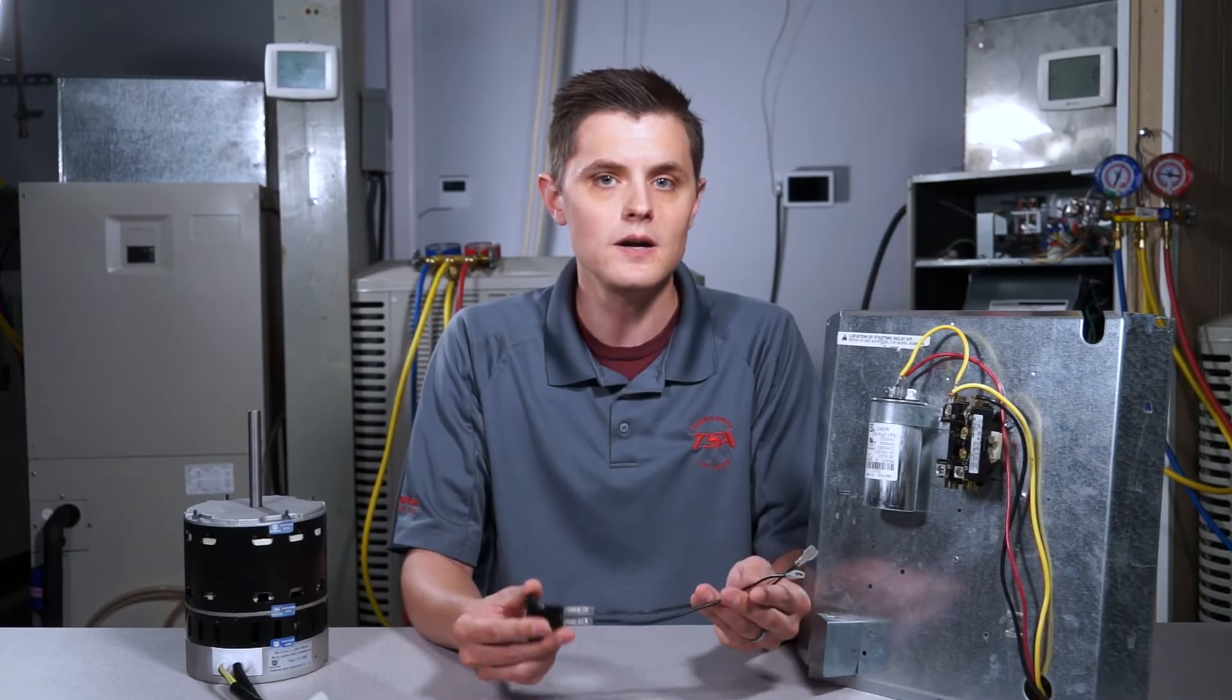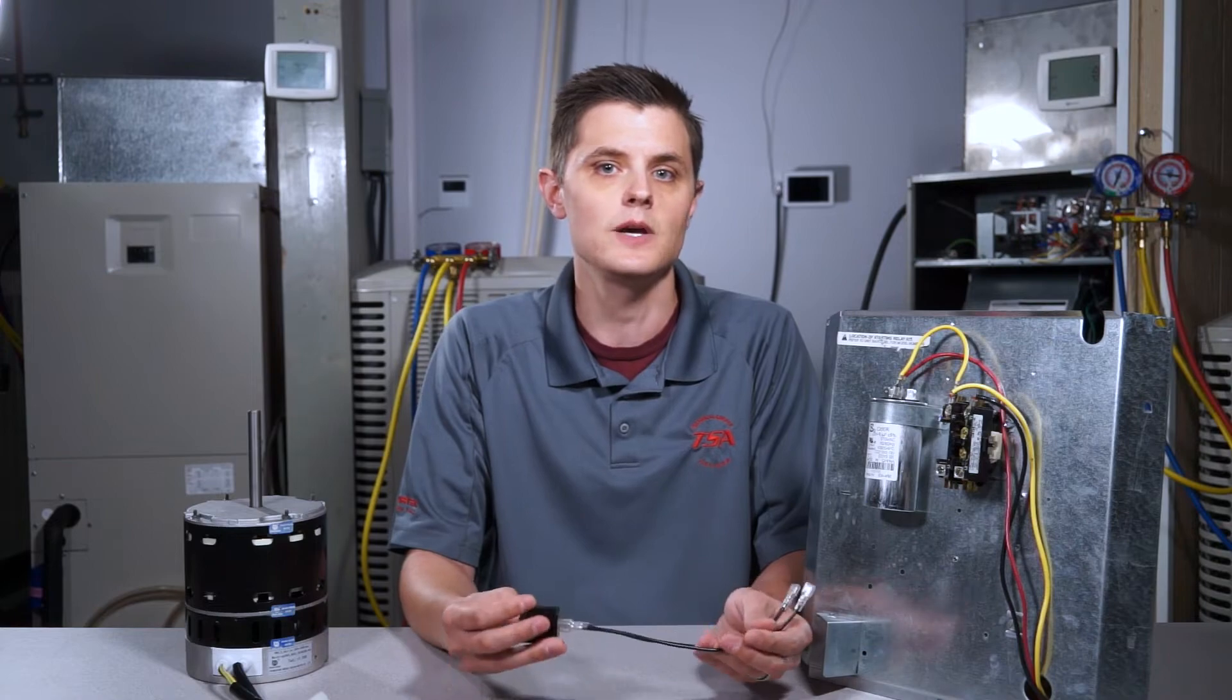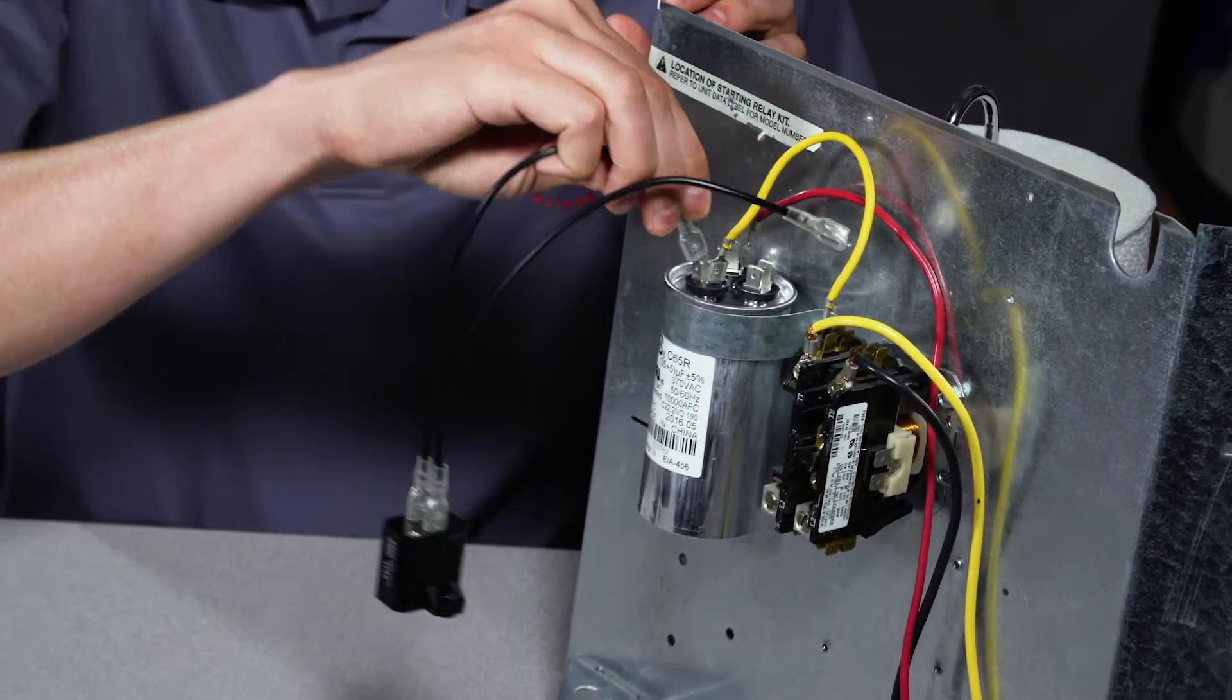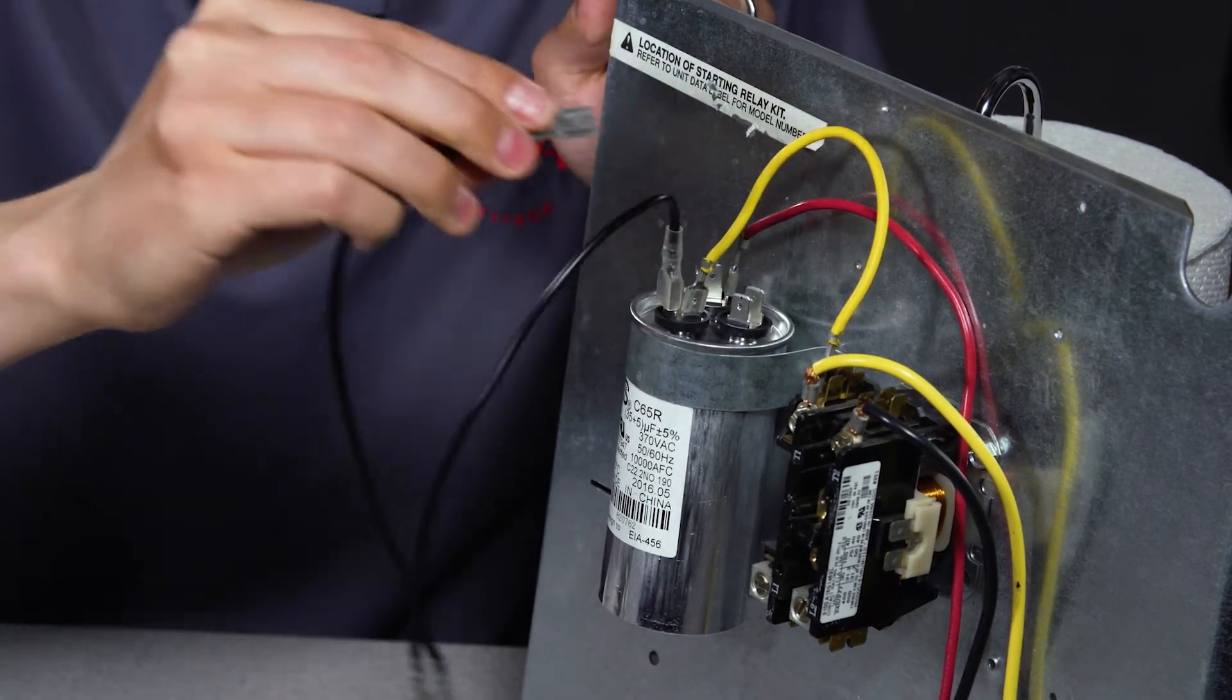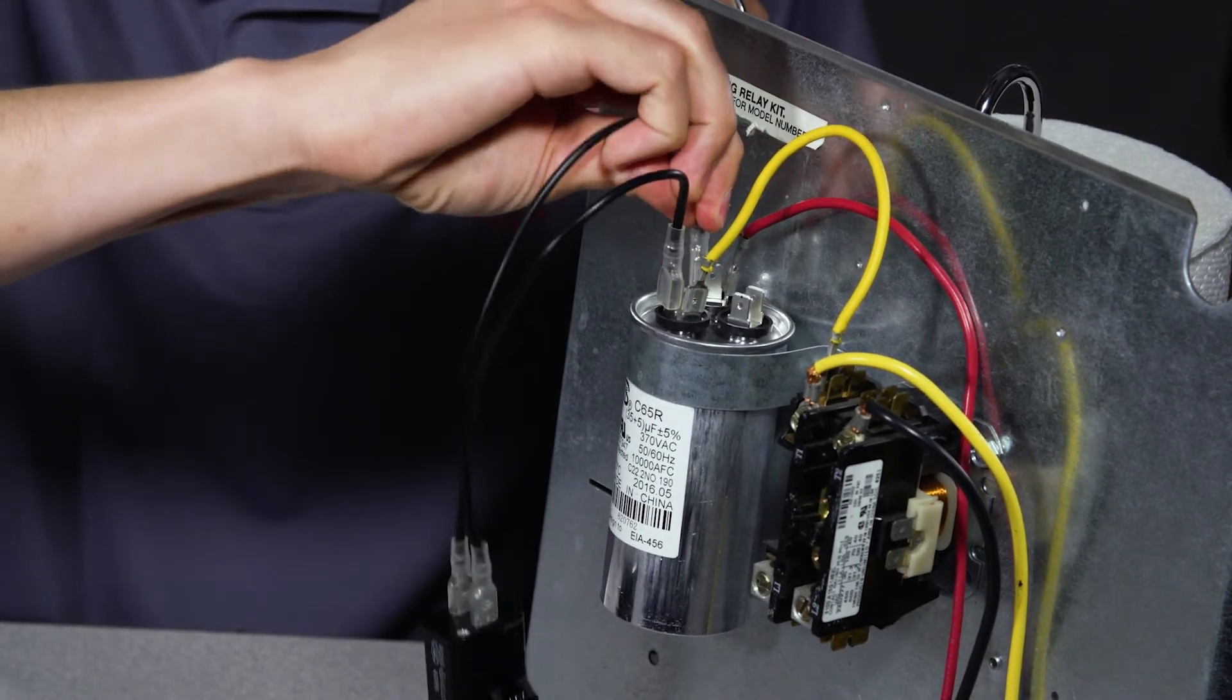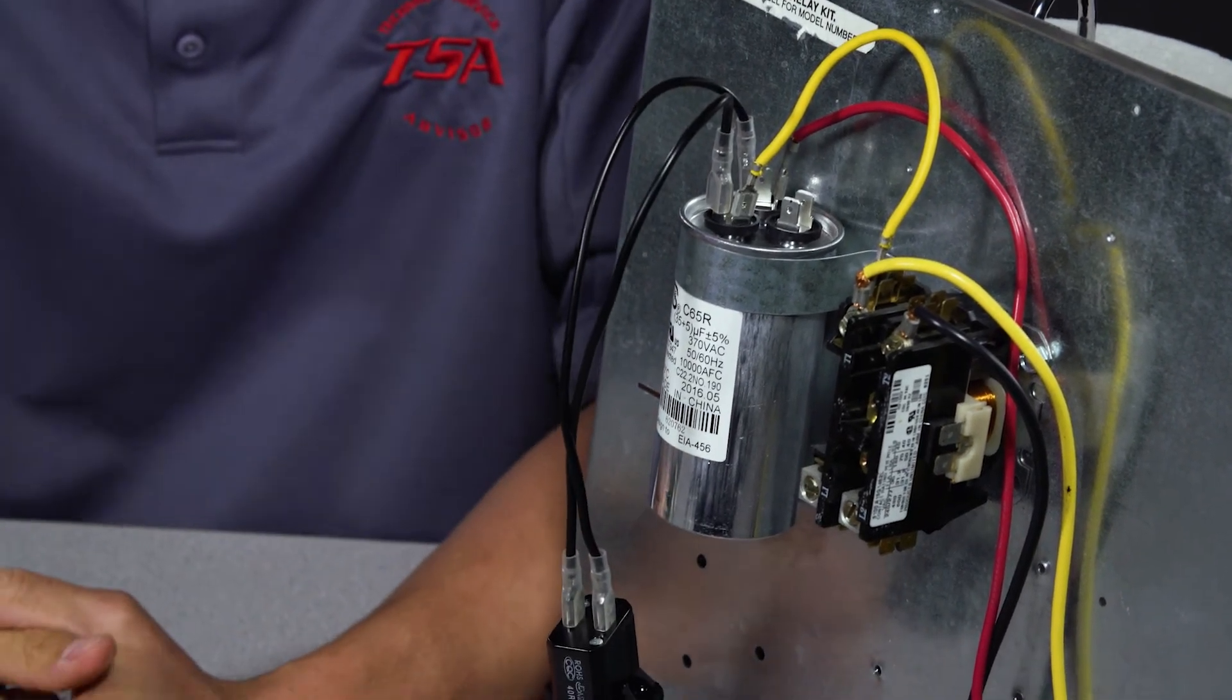When you wire this part into the unit, it wires in exactly the same as the previous part. You'll pick one of your two wires—one will go to Common and one will go to Herm. It doesn't matter which wire you pick, just Common and Herm on the capacitor and you'll be good to go.